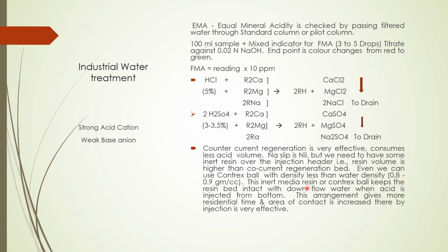This inert media, whether it is resin or Contrex balls, keeps the resin bed intact. Downflow of water is used. When acid is injected from the bottom, downflow is kept from the top inlet line to the injection outlet. This arrangement gives more residence time and the area of contact is increased, thereby regeneration is very effective.